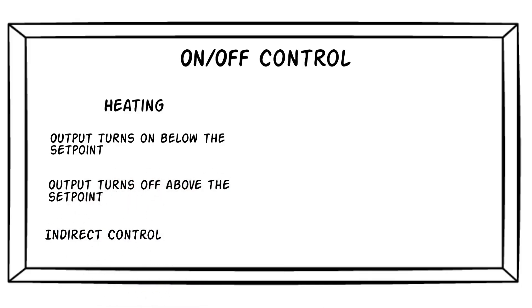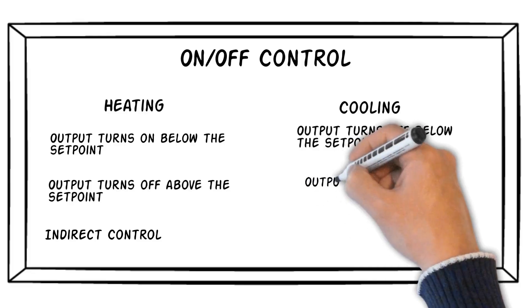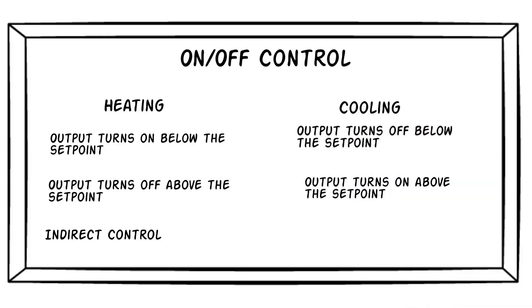It's called indirect acting control because as the temperature goes up, the power to the heater goes down. In a cooling application, the output is turned off below the set point and turned on above the set point. This type of action is called direct acting control.